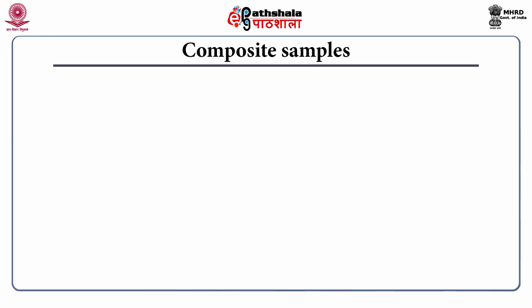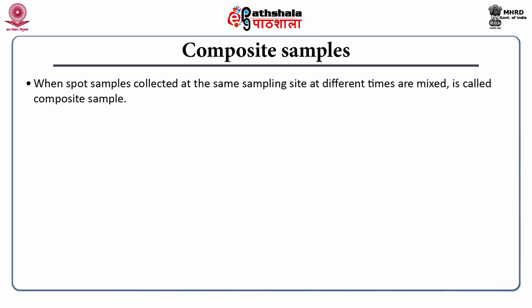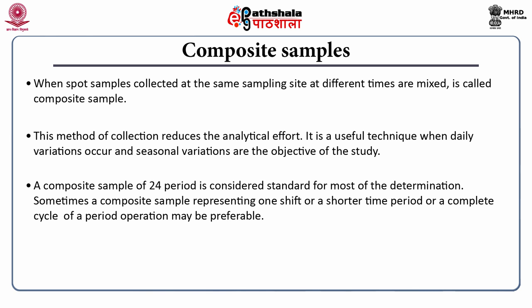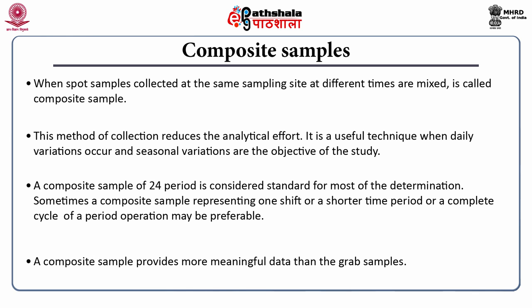A composite sample is formed when spot samples collected at the same sampling site at different times are mixed together. This method reduces analytical effort and is useful when daily or seasonal variations are the objective of study. A composite sample of a 24-hour period is considered standard for most determinations. Sometimes a composite sample representing one shift, a shorter time period, or a complete cycle of a periodic operation may also be preferable.